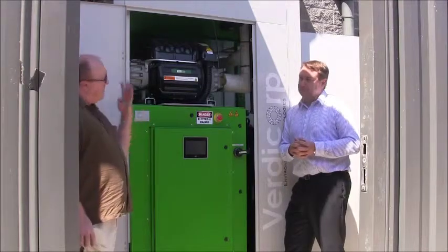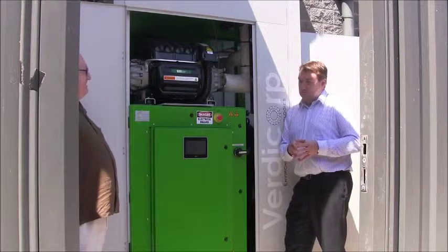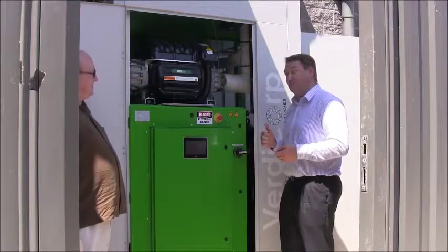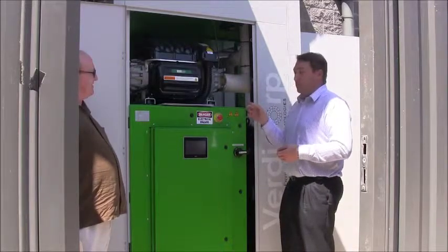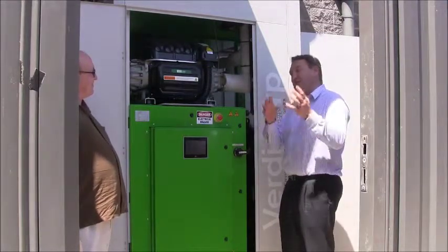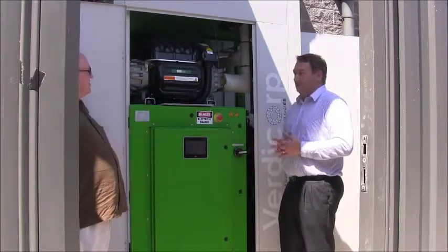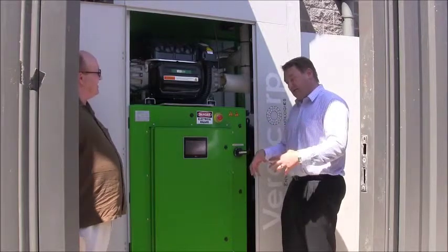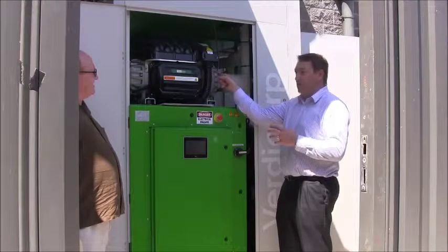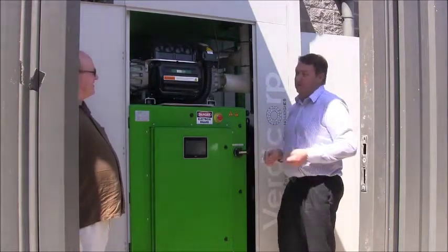Now the important question: in four sentences, explain what an ORC is. It's a Rankine cycle turbine that uses a high molecular mass fluid — a refrigerant. We boil the refrigerant, we make high-pressure gas, we turn the turbine, we condense the gas back to a liquid, and we pump it back to the start of the cycle again. So the heat going in heats the fluid, boils it to turn it into a high-pressure gas to drive the turbine wheel, and then the other side of the cycle condenses it back to liquid and pumps it back around.